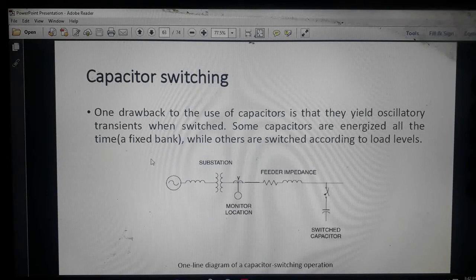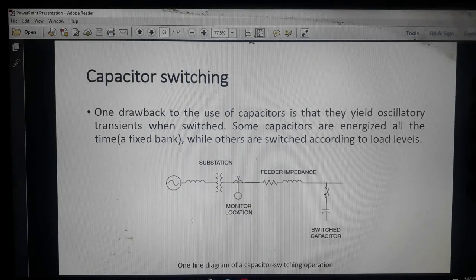First, we have to take some cases which are responsible to generate transient over voltage. First is capacitor switching, as shown in the figure. This is the substation, monitor location, feeder impedance. This is the capacitor. This is the switch. Through the switch we connect the AC bus to the capacitor bank.